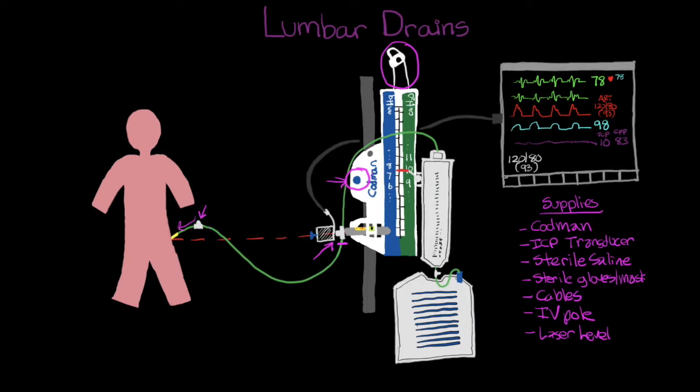Now at this point, you're going to want to turn the patient stopcock down here and turn it off to the end of the tubing. And then go up to your panel stopcock, and now you're going to want to turn it off to the drain itself. And you want to go ahead and flush now with the saline down the tubing, and this will cause it to come all the way up and out the end of the transducer here.